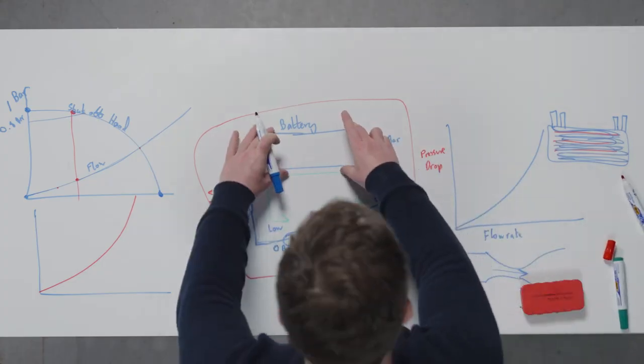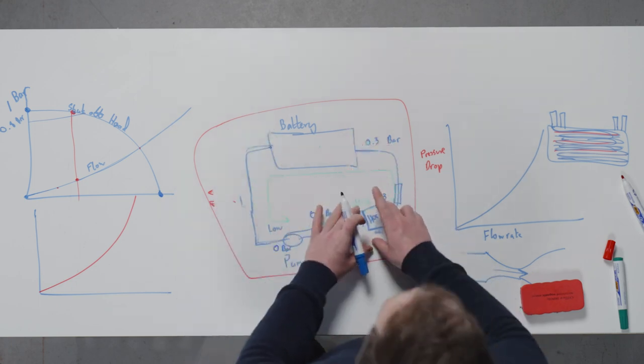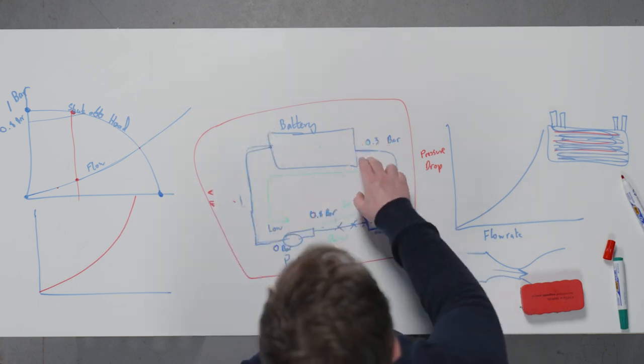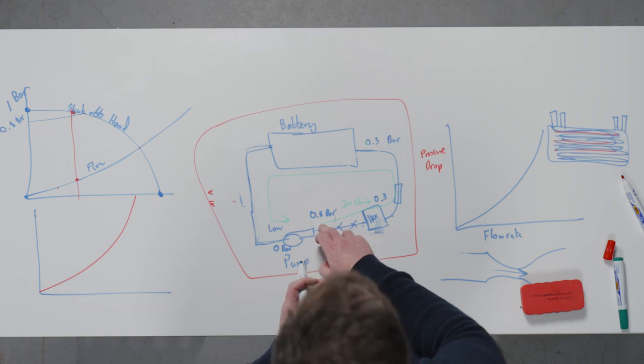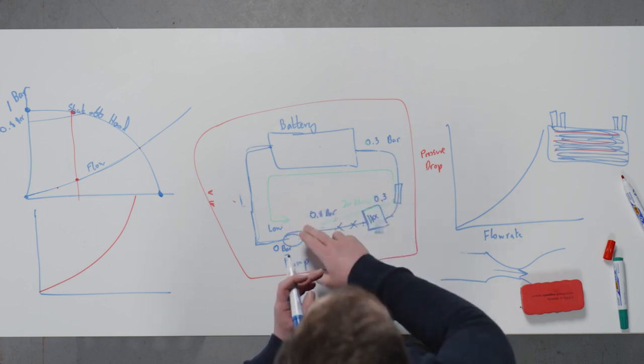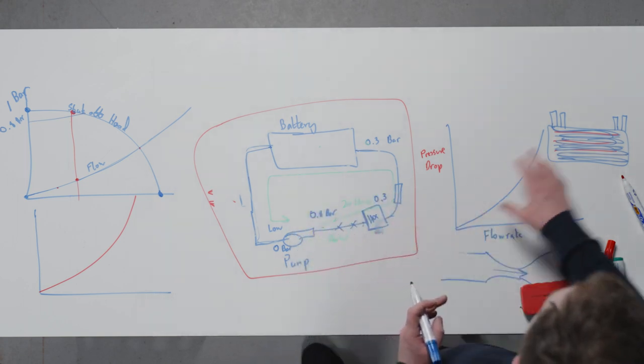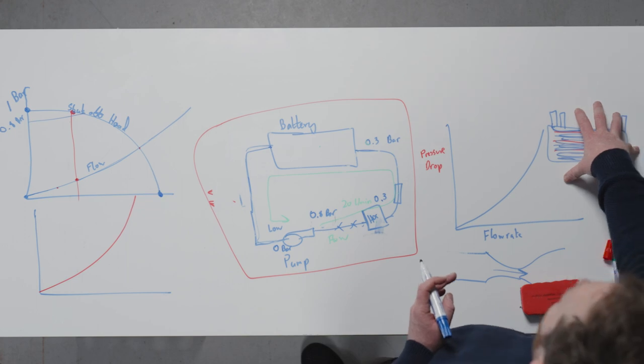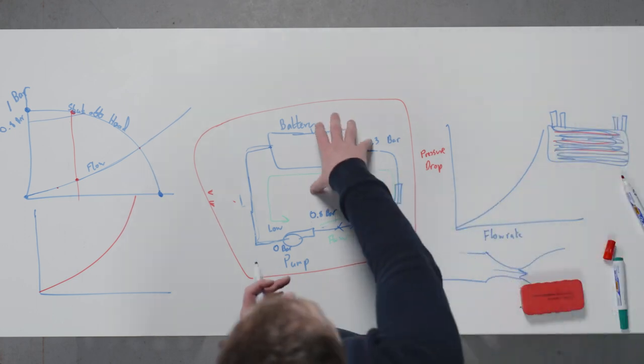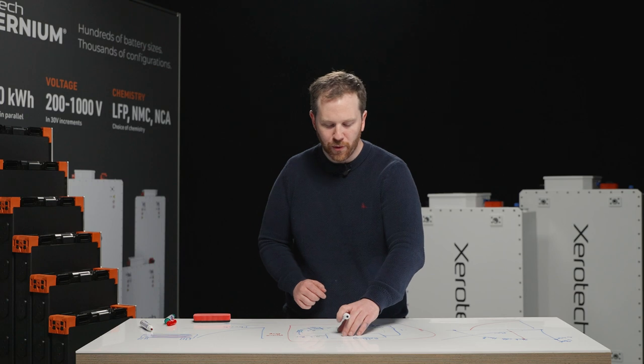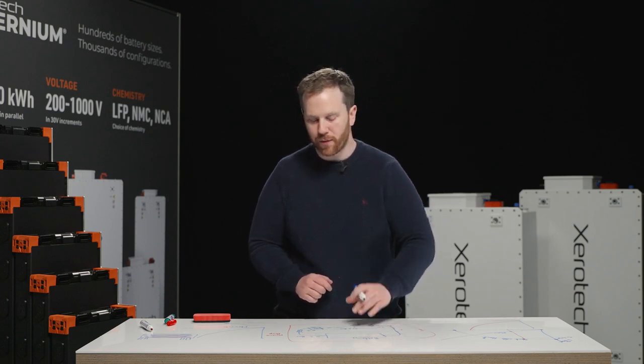But if I were to move this battery from here to directly in front of the pump, it'll be seeing double that pressure, nearly triple that pressure for the exact same flow rate. That pressure doesn't matter at all for a solid block of metal like a plate heat exchanger, but it does matter for a Xerotech battery. So you always want to make sure it's on the right side of the system.